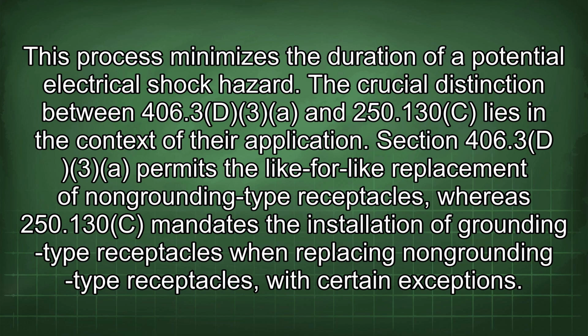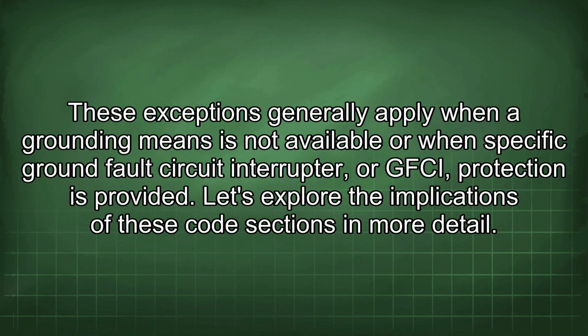The crucial distinction between 406.3d3 and 250.130c lies in the context of their application. Section 406.3d3 permits the like-for-like replacement of non-grounding type receptacles, whereas 250.130c mandates the installation of grounding type receptacles when replacing non-grounding type receptacles, with certain exceptions. These exceptions generally apply when a grounding means is not available or when specific ground fault circuit interrupter, or GFCI, protection is provided. Let's explore the implications of these code sections in more detail.